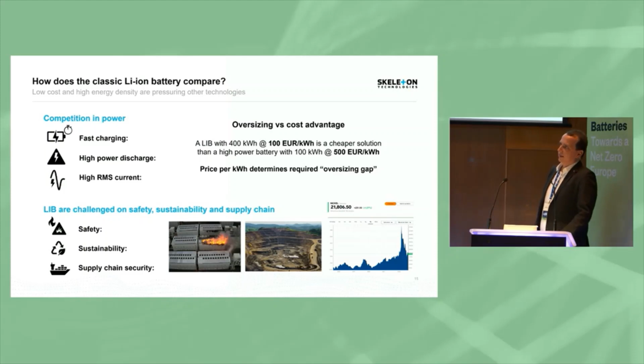But in the end it's a question of oversizing, and if you think about oversizing, the commercial part comes into play. For example, if you need a 400 kilowatt-hour battery at a price of 100 euro per kilowatt-hour, it's actually a cheaper solution than a 100 kilowatt-hour battery using a high power battery at 500 euro per kilowatt-hour for 100 kilowatts. In the end this is the gap in oversizing where you need to find the right balance for the application, and I'm going to show you on the next slides our view on this for the future.